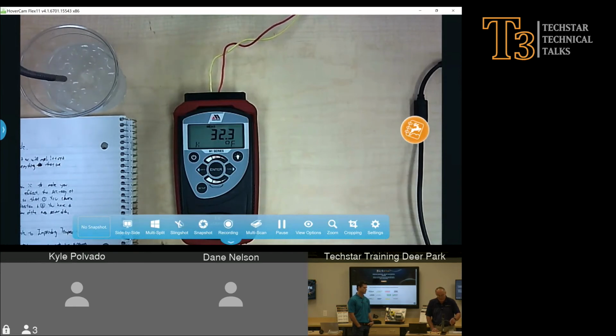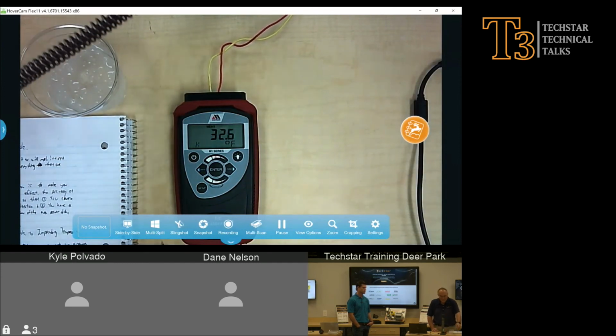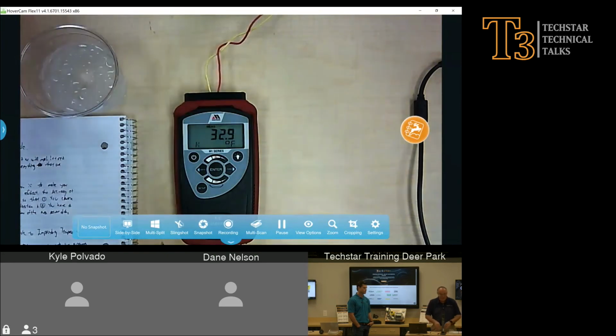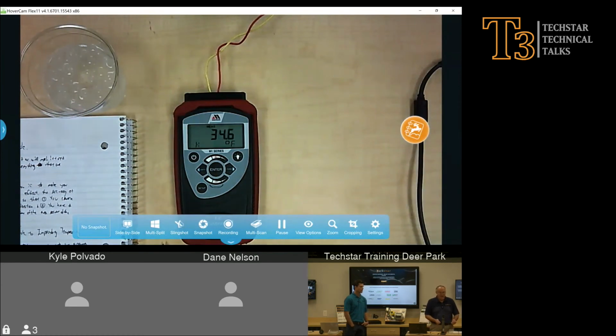For the Texas Clean Air Board or something else, I'm sure you probably have to send it off for a calibration, and they would do multiple points, and you get that point either in a resistance format. I'm assuming you're using an RTD, or if you have a transmitter, they would calibrate the whole thing, which is recommended. Temperature baths are just easier, and almost all smart transducers have the ability to do what we call trim, but you can adjust some center points. A point of interest is RTDs are quite a bit more linear than thermocouples. So usually if you get a good 0 ice bath, you're going to be in pretty good shape.